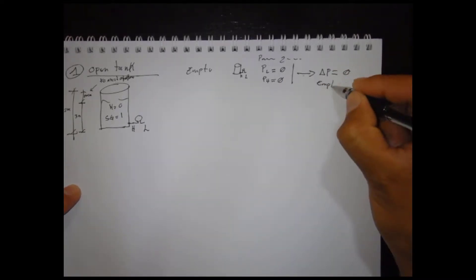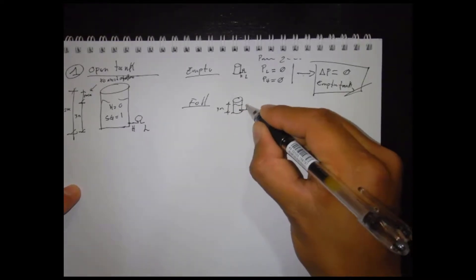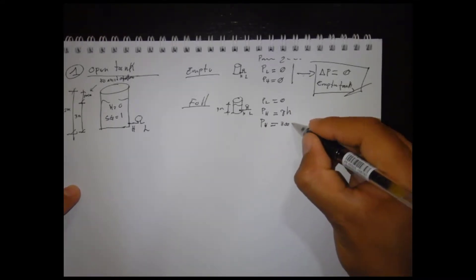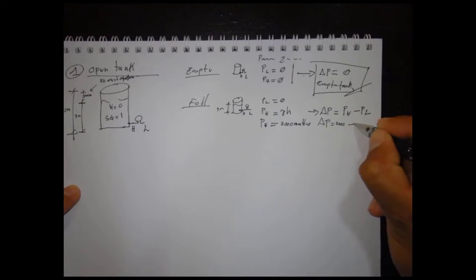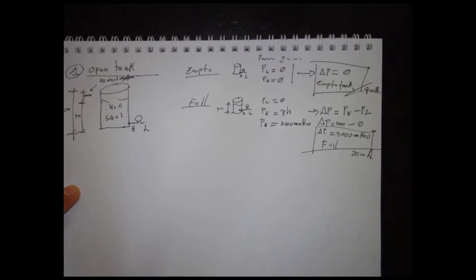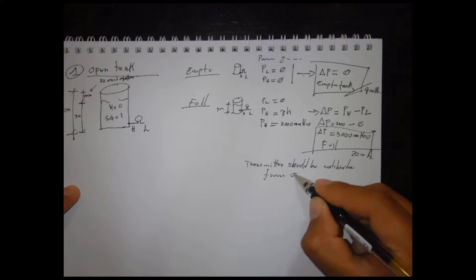If the tank is empty, the pressure on the L side is zero and the pressure on the H side is also zero. If the tank is full, the pressure on the L side is zero and the pressure on the H side is equal to 3000 mm of water. Then the differential pressure read by the transmitter is equal to 3000 mm of water for a full tank, and that will correspond to 20 mA. The transmitter should be calibrated from zero to 3000 mm of water.